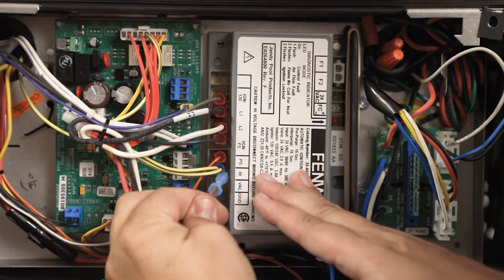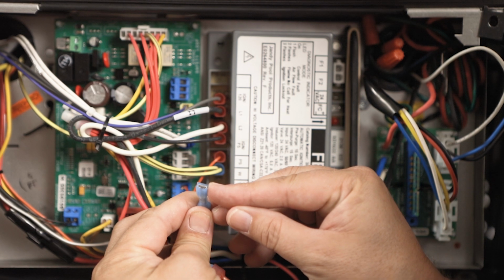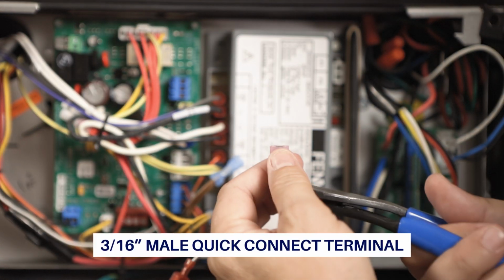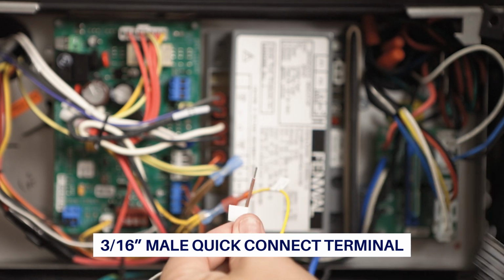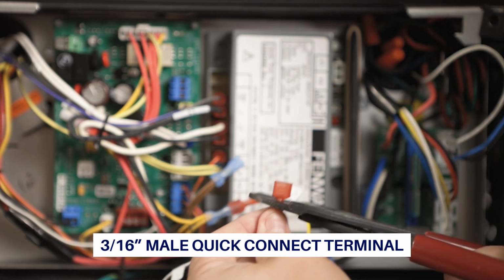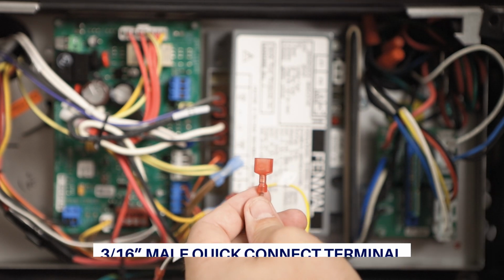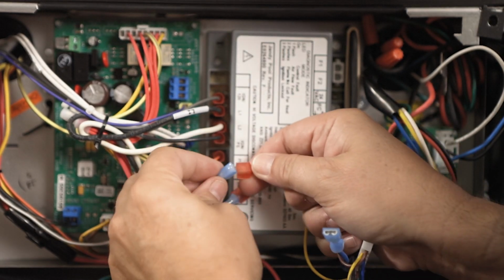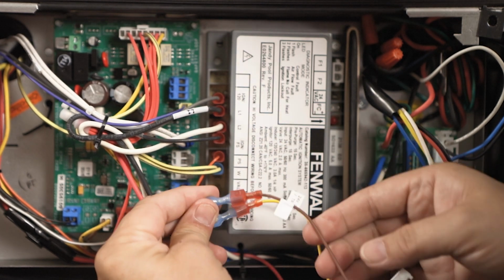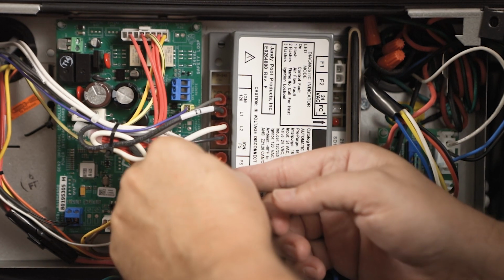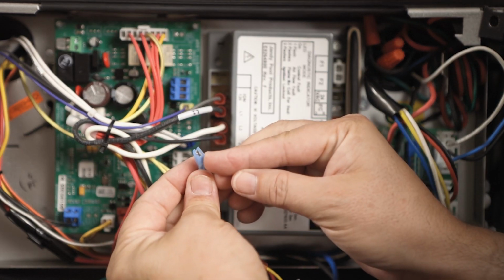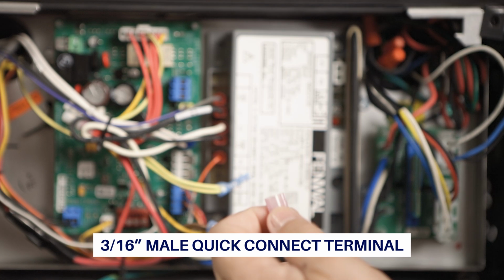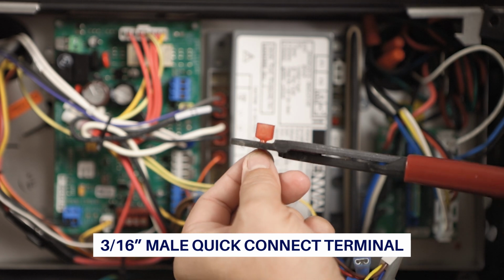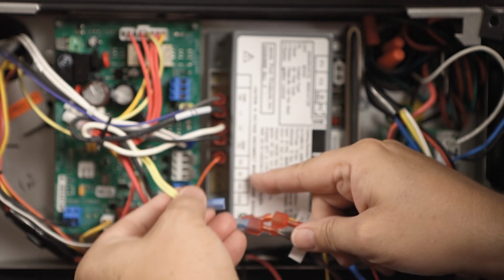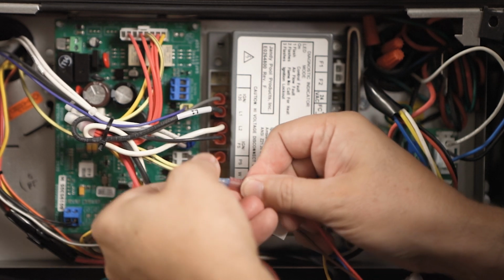Remove the wire from the VAL terminal. Note if it is a 1/4-inch or 3/16 spade connector. The 11-pin harness MV1/valve Quick Connect 1/4-inch male spade must be replaced with a 3/16 male spade to accommodate the existing 3/16 connector spade. Connect the VAL wire to the 11-pin harness wire labeled MV1/valve. Remove the wire from the W terminal. Note if it is a 1/4-inch or 3/16 spade connector. The 11-pin harness THW Quick Connect 1/4-inch male spade must be replaced with a 3/16 male spade to accommodate the existing 3/16 connector spade. Connect the W wire to the 11-pin harness wire labeled THW.